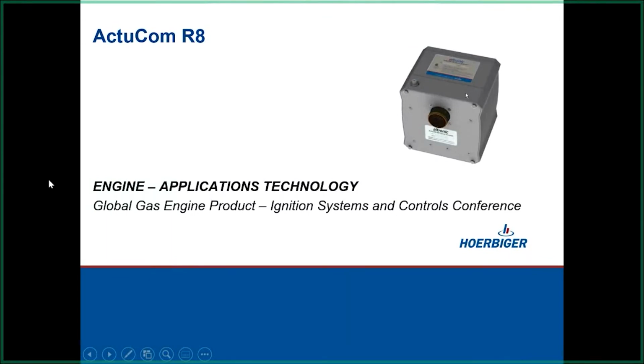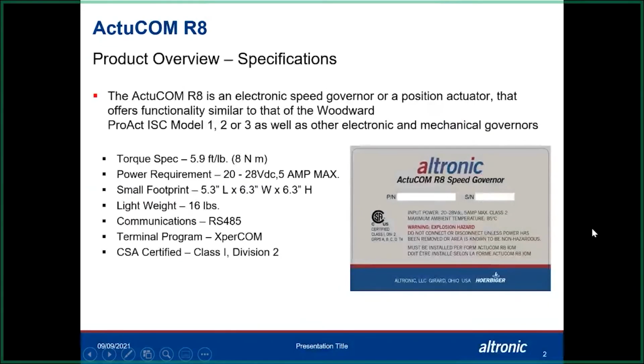All right, a lot of y'all have probably already seen this. We're going to try to cover a little bit of this ActuCOM electronic governor for our carbureted engines. It's also an actuator that we can use standalone for any kind of position control. It's a 24 volt powered electric motor, basically DC. It has 5 amps on the power requirement, and that's something for your sales guys we really need to pay attention to, because if we're selling against brand X, typically they have a little bit higher power requirement than we do. I've seen some go up to nearly 20 amps on the competitors' products, which makes it a lot more desirable to stay with the 5 amp.